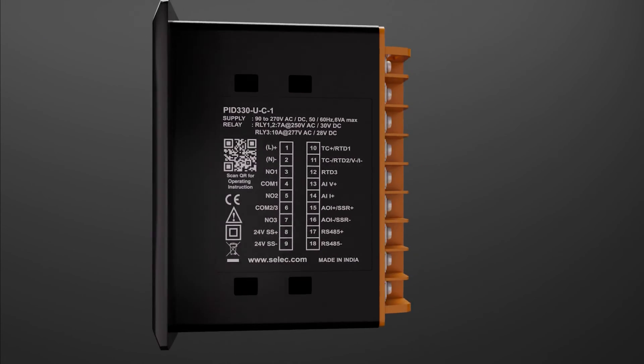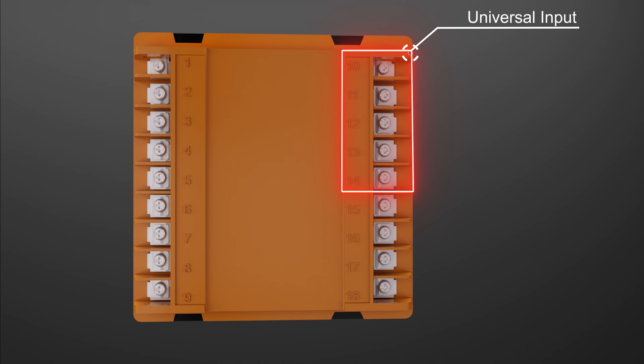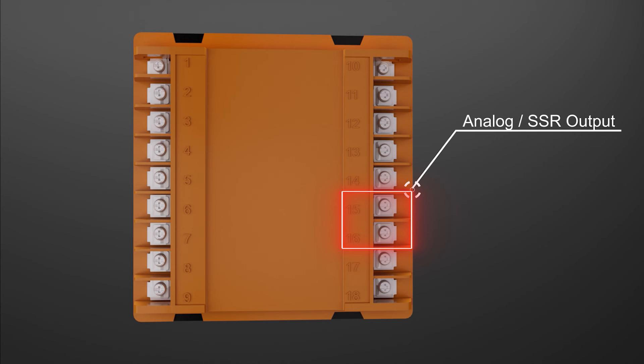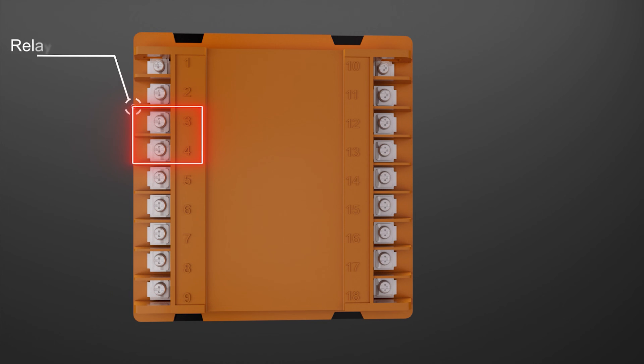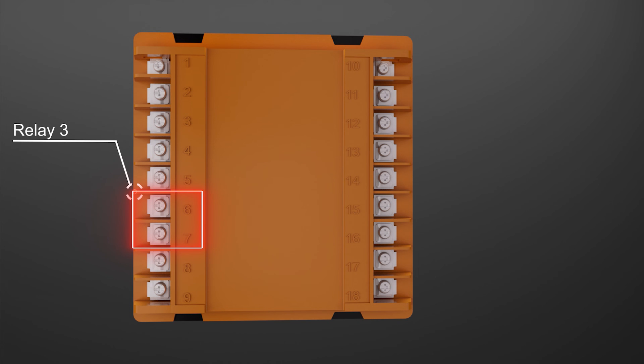For PID 330U: Terminals 1 and 2 for auxiliary supply. Terminals 10, 11, 12, 13, and 14 for universal input. Terminals 15 and 16 for analog current, voltage, or SSR output. Terminals 17 and 18 for RS-485 Modbus communication. Terminals 8 and 9 for sensor supply. Terminals 3 and 4 for relay 1 output. Terminals 5 and 6 for relay 2 output. Terminals 6 and 7 for relay 3 output.